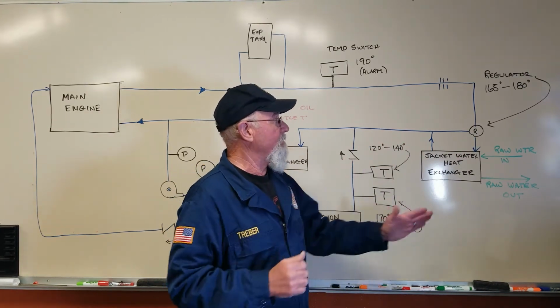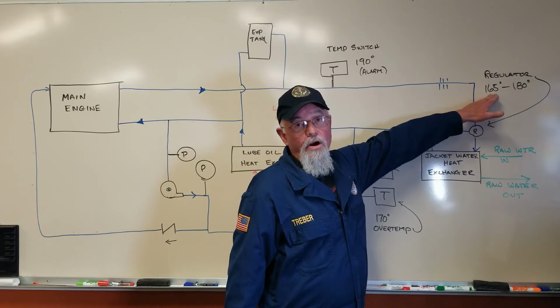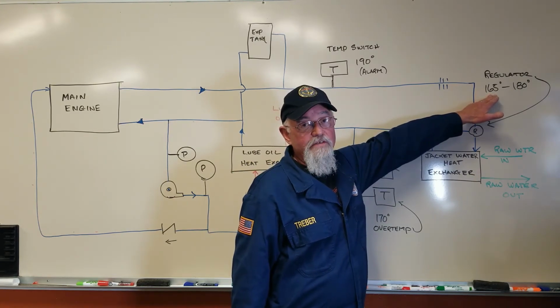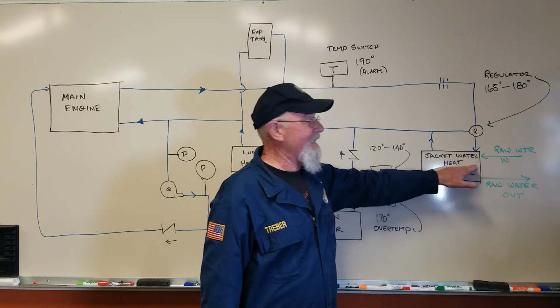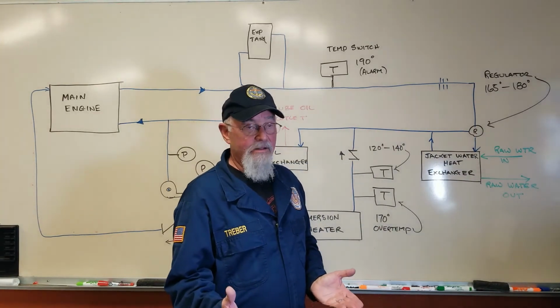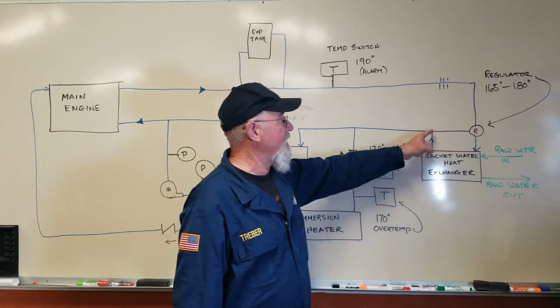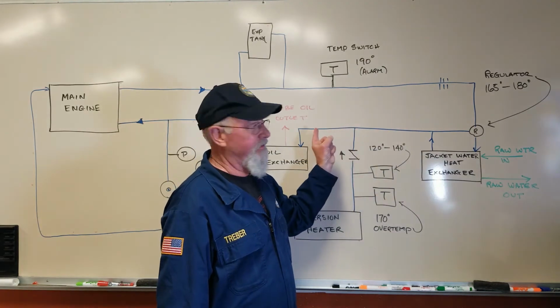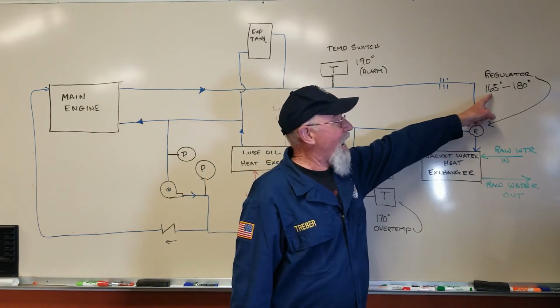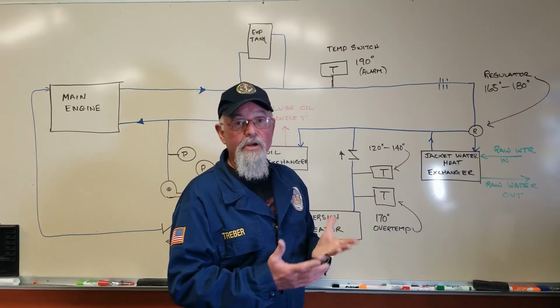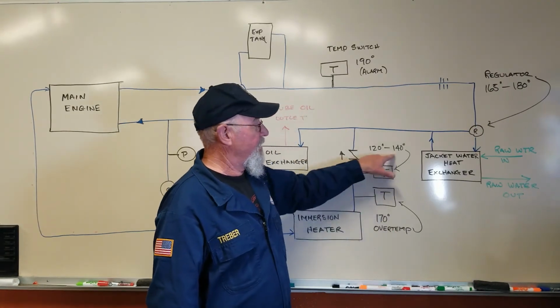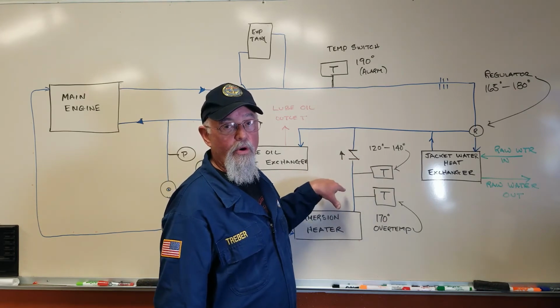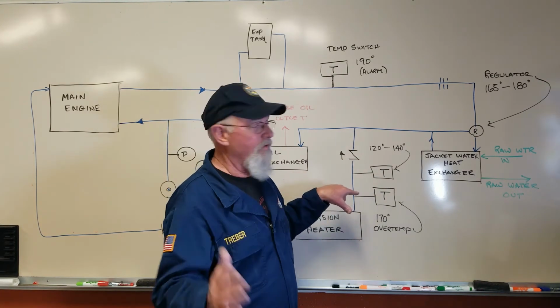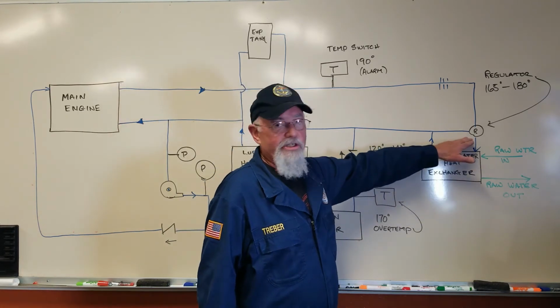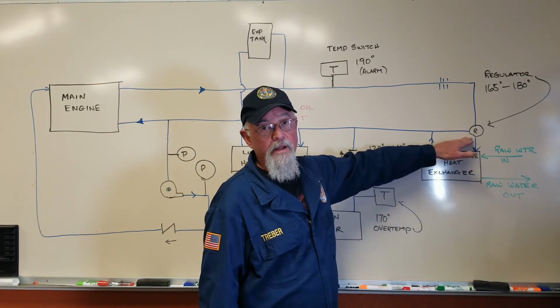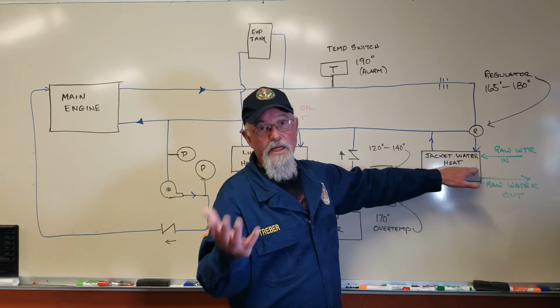So here's the assumption. If the jacket water temperature is 165 or less, we don't need to get rid of any heat. So the jacket water will be redirected in this direction. Now this would normally happen when the engine's running, because this is going to maintain this temperature at 140 max, so between 120 and 140. So we should never really see the regulator start to open to the cooler or the heat exchanger.